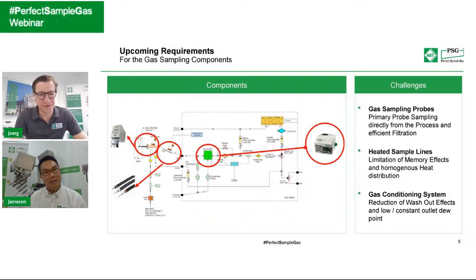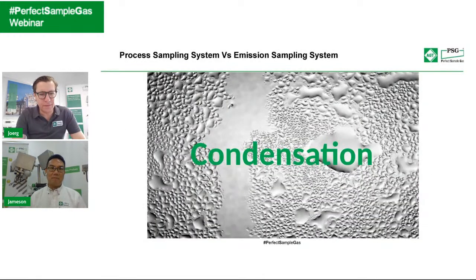Yeah, and the complexity, I think, also outlines this. That's the reason why I put up the P&ID here again, in order to show where the cooler is, where the gas sampling pump is positioned, and how all of this is combined together. So, like you said, Jameson, somehow we have to speed up a little bit for the gas sampling probe. We have two situations, I think. The one situation, which you already touched on in the introduction, is that we might have a probe or process temperature which is way higher than the heating of the gas sampling probe. That could be the first thing. And maybe you can say some words about this.